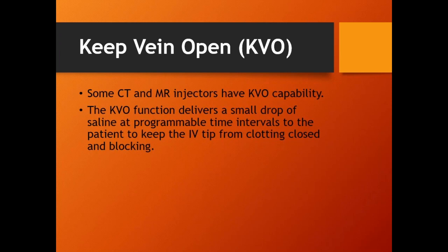Yeah, this one does. Some of it's like a single tube going to the patient, but it's got to be dual, right? So it's a dual. You're running both to the end of that. Yeah, and that's always the case. There's never a separate tube for each one. They always come together close to the contrast syringe, typically, to deliver out the single tube.